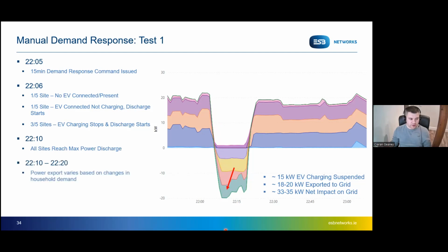vehicles. And then from 22:10 to 22:20, the exported power to the grid varies based on how much the household is consuming, and we see the site here in red. Its consumption varying, altering how much was going out onto the grid. By 22:21, we had the end of our test, and the 3 locations that were charging resumed charging. But what's really important to note here was the net change in power flow across these sites. So we had between 33 and 35 kilowatt net impact on the grid from the 5 locations where we had V2G. That's really important in terms of the potential for this technology going forward and the capability that it can provide, even compared to the domestic battery systems, which typically have smaller inverter ratings and definitely a much lower energy capacity.